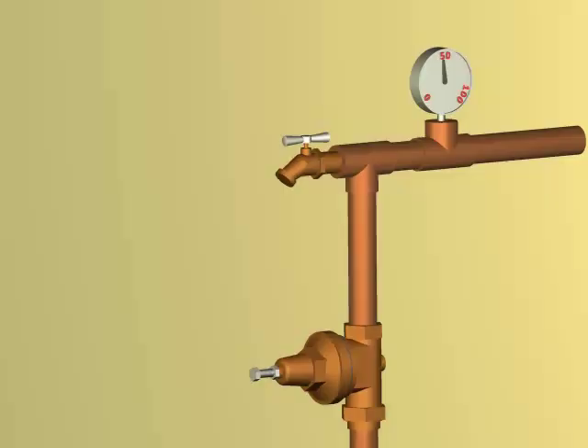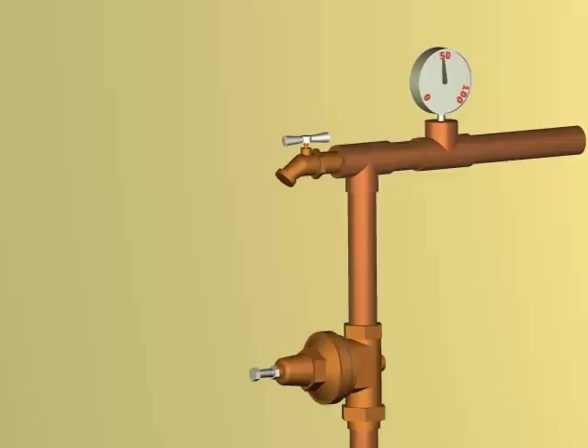You can now tighten the lock nut when your desired pressure is set. You will then observe your gauge for a few minutes to make sure pressure is constant, showing that the ring cartridge and O-rings are seated properly and that there are no internal leaks in the valve.